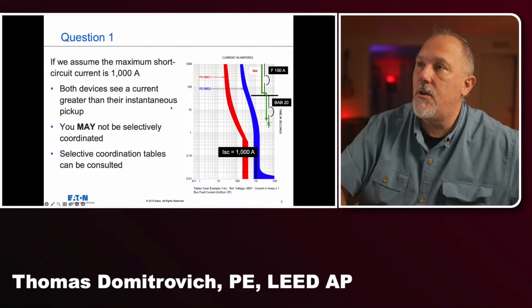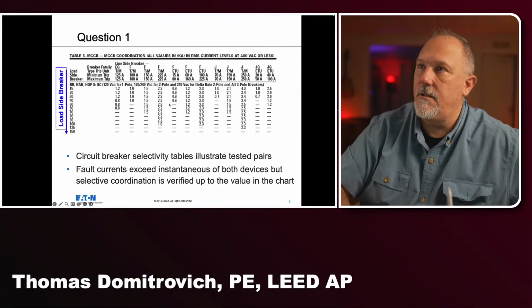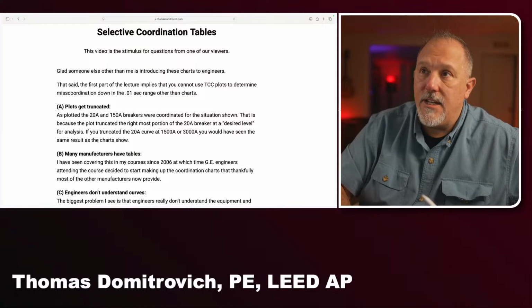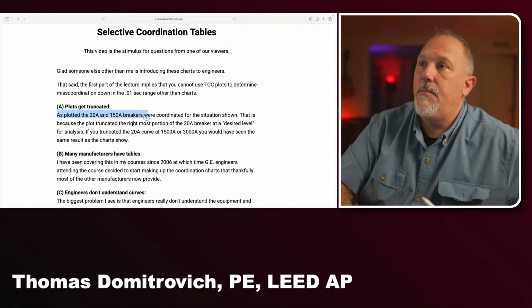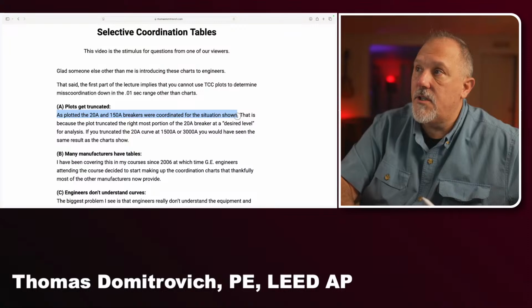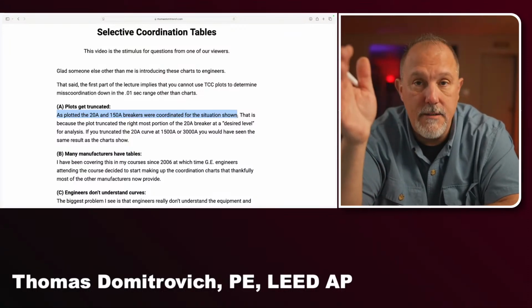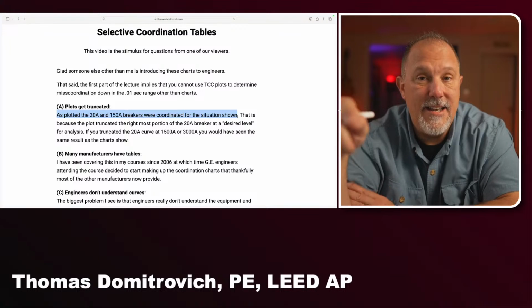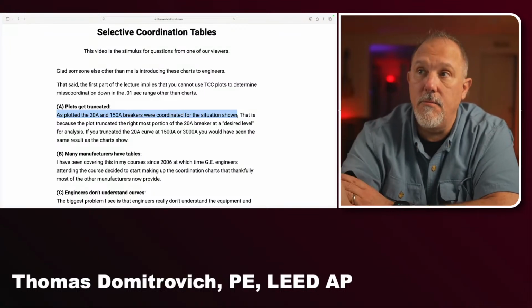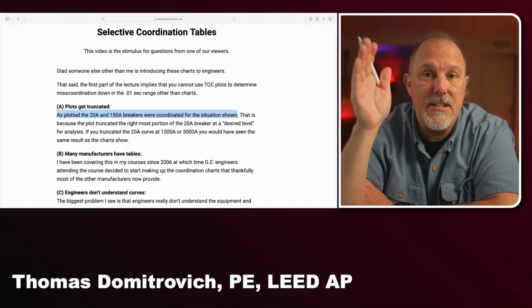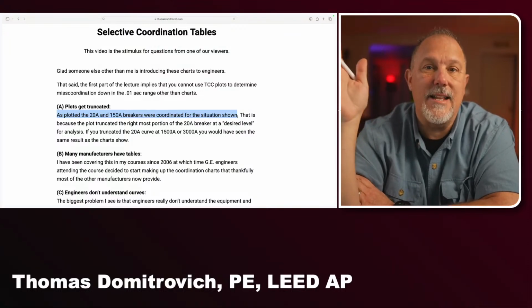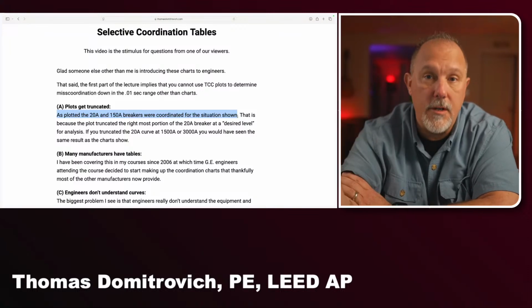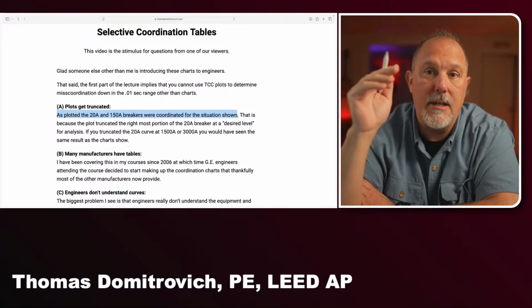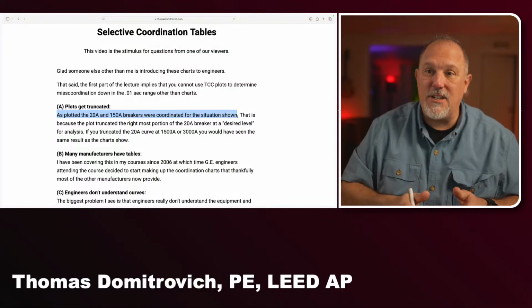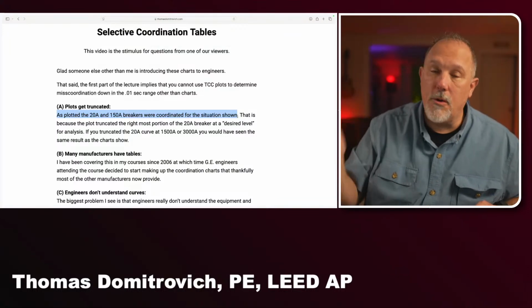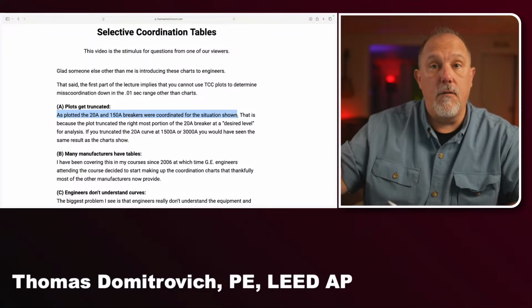All right? So if I go back to the question, as plotted, the 20 amp and 50 amp, 150 amp breakers were coordinated for the situation shown. Now, coordinated, I would say yes. If he's using the term coordination and not selective coordination, then coordination is not selective coordination, because selective coordination is for all currents, all times. Coordination could just be in the overload region, right?